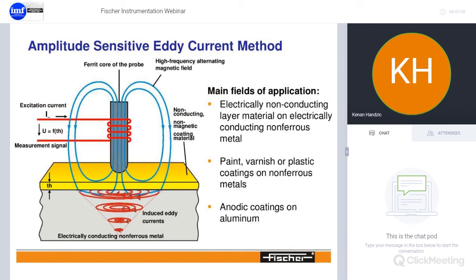For the eddy current method, there is only one coil around the probe, used as both the excitation and detection coil. The fields of application are non-conducting layer material on electrically conducting non-ferrous metal — we're looking at paint, varnish, and plastics on non-ferrous metal, or anodic films on aluminium, for example.